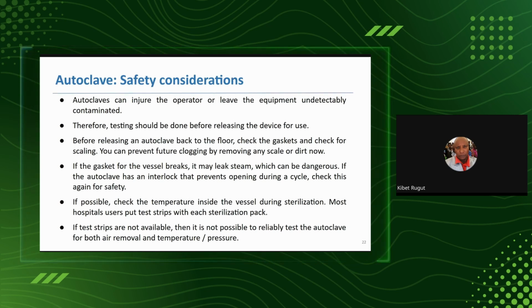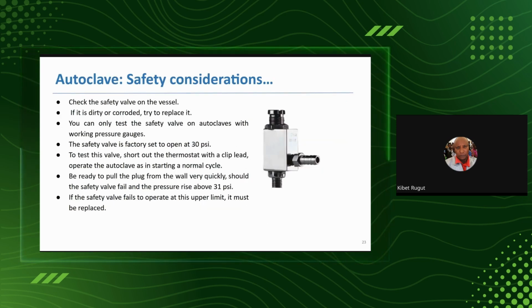Then, regarding the temperature in the vessel during the sterilization cycle, it is good to do even non-loaded tests so that you know very well that, even without loading, it attains the temperature that you want. Safety valves are very, very crucial. You can even sometimes find safety valves that have been adjusted and a padlock placed on them. Sometimes they are small, miniature like this. So it is good to test again according to the maintenance manual or technical manual.